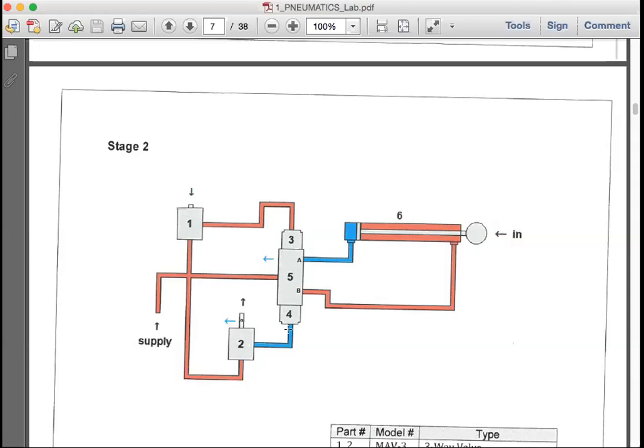So nothing would change inside the valve because you have the equal and opposite pressure on the other side. So pressing the second valve once one valve is still pressed is not going to change the position of the stem in the valve, nor the position of the piston in your cylinder.